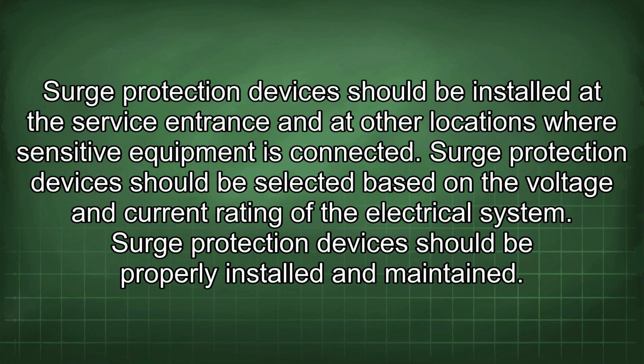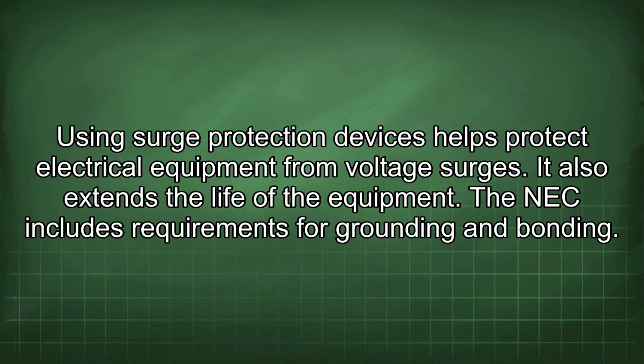Surge protection devices should be installed at the service entrance and other locations where sensitive equipment is connected. They should be selected based on the voltage and current rating of the electrical system, and should be properly installed and maintained. Using surge protection devices helps protect electrical equipment from voltage surges. It also extends the life of the equipment.